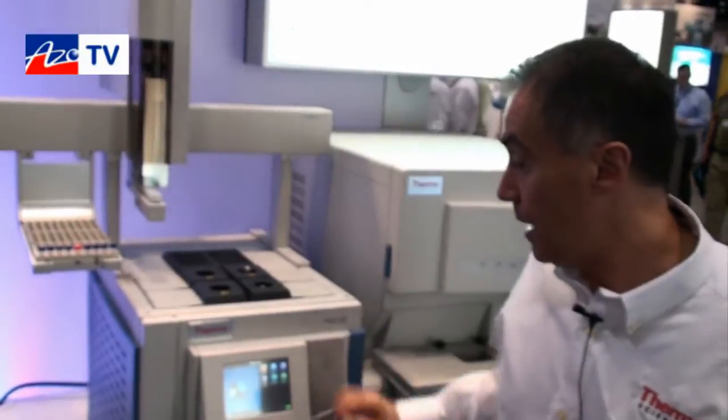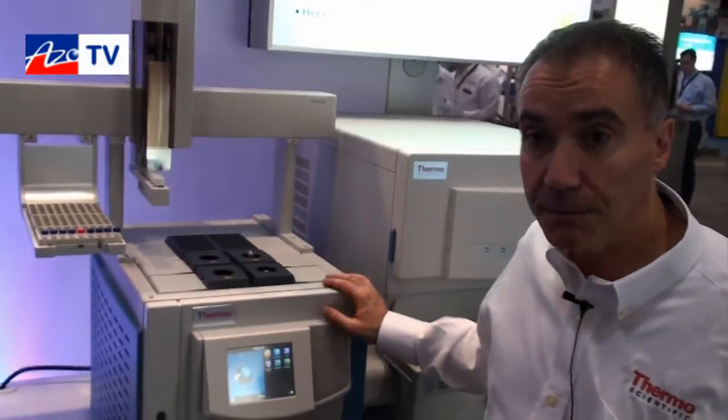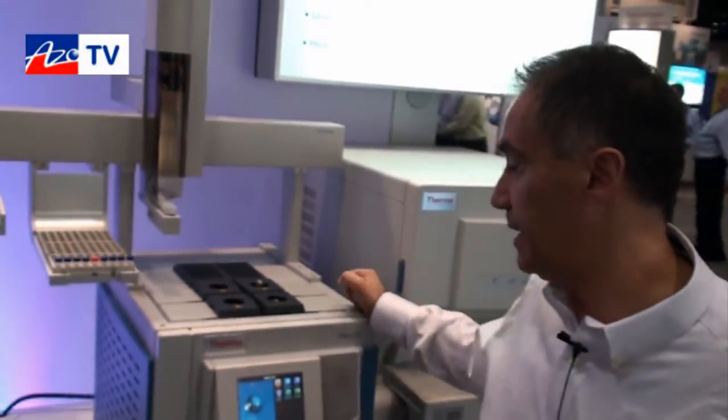Of course, if you are able to produce more analyses in the same amount of time, you are able to increase the productivity of the laboratory. The instrument is designed by reducing the thermal mass of all the components, so the time for the instrument to reach a ready condition after power-up is only 3 minutes. Existing instruments in the market take between 15 and 20 minutes once powered up to reach steady conditions.